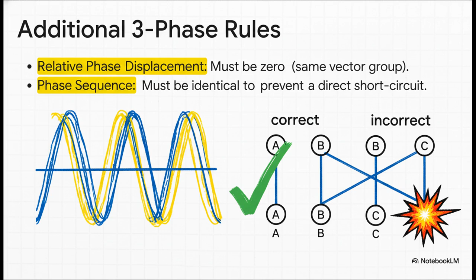So we've gone through a whole bunch of rules here, but what actually happens if you break them? What are the real-world consequences when you don't check all these boxes? Well, the cause and effect is pretty clear. If your voltage ratios don't match up, you get that circulating current we talked about, just pointlessly generating heat and wasting power.